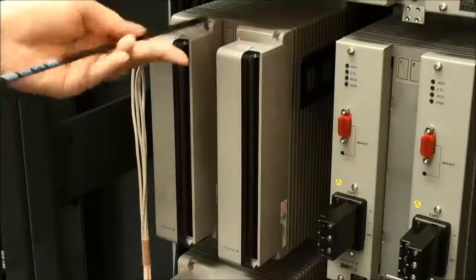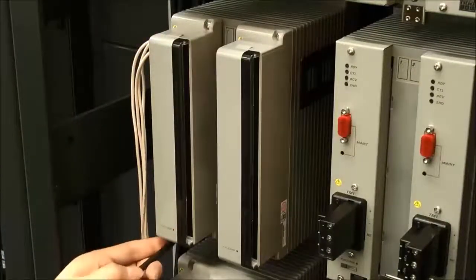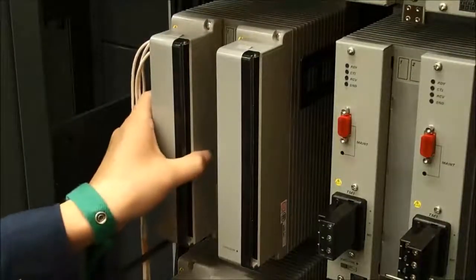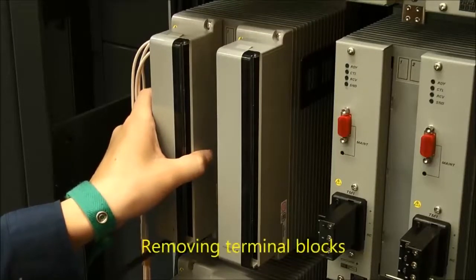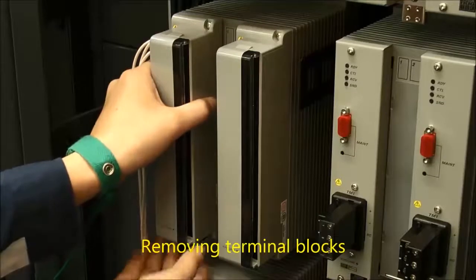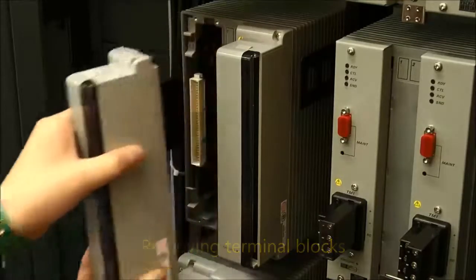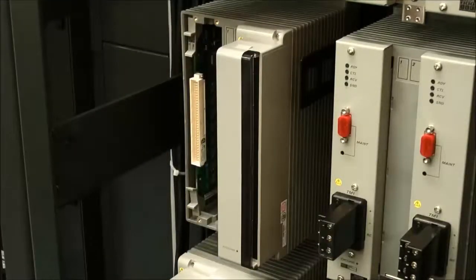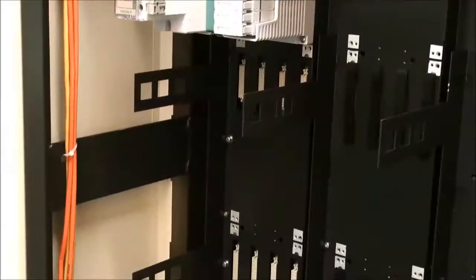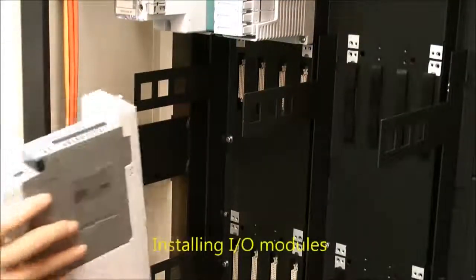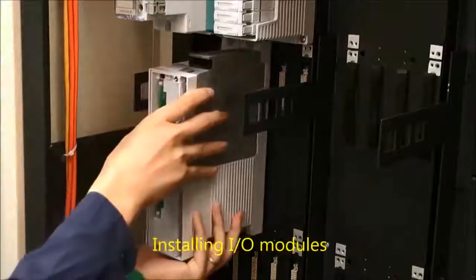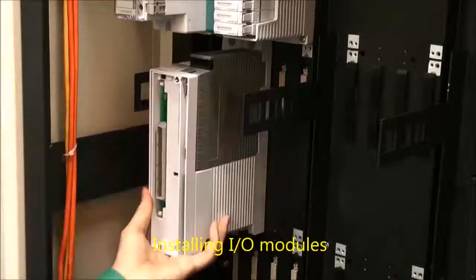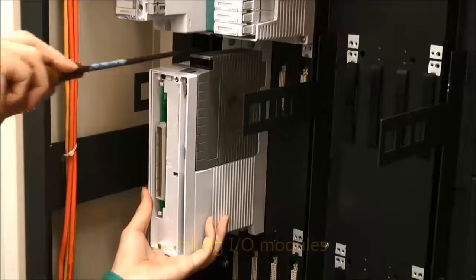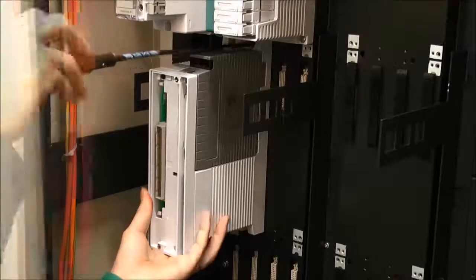A multi-point multiplexer module does not require disconnection of signal cables. The existing terminal block is usable as it is. With the signal wires still connected, separate the terminal block from the I/O module. After mounting a new module on the node, fix the separated terminal block on the front of the module. This completes the replacement process.